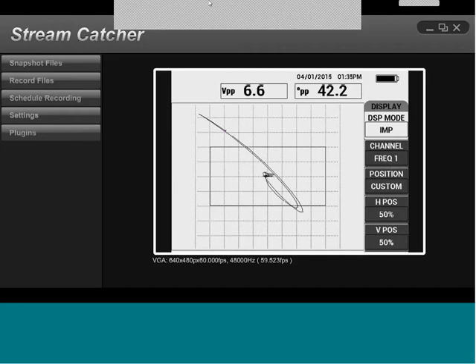I can also change the displays, go to a pure impedance plane, and freeze my display. Nothing prevents me from adjusting the angle a little bit better, because we have this new feature on the NORTEC called calibration from frozen signal. So right now I can tune my angle to be a little bit better adjusted. As I unfreeze the equipment, I will just get a better signal.